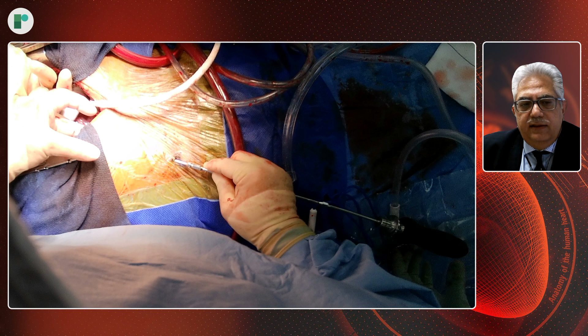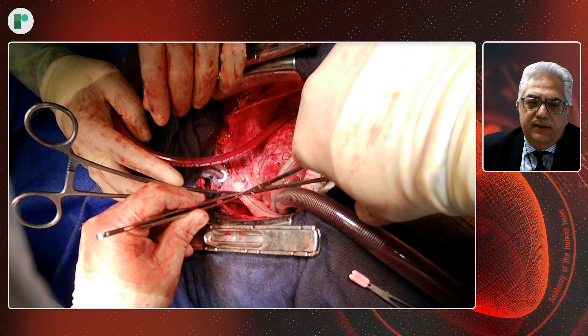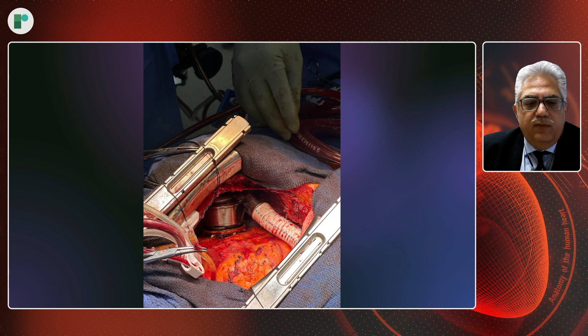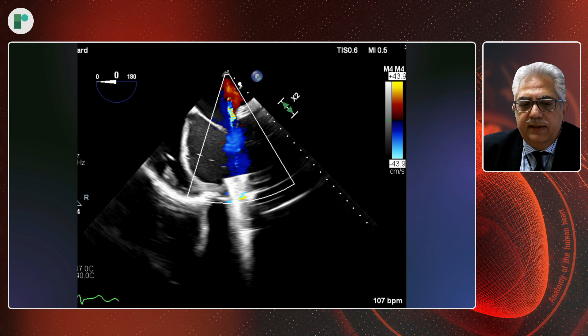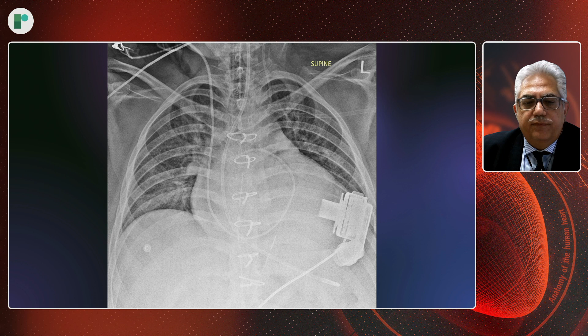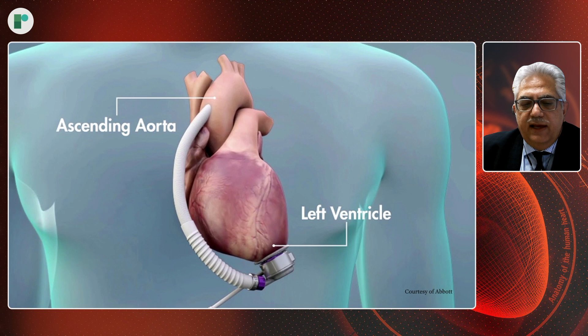Then it's time for the outflow tract to be sized and de-aired with a heart full, and then it is anastomosed with a side-biting clamp onto the ascending aorta with sutures. That is usually placed at about a 45 degree angle to the aorta. And this is what you will see at the end of this operation. That's the TOE image showing the Doppler flow of blood through the pump head, which you can see here. This is the X-ray of the same, and that shows the arrangement of the pump head and the outflow tract, and you have got the drive line going there.